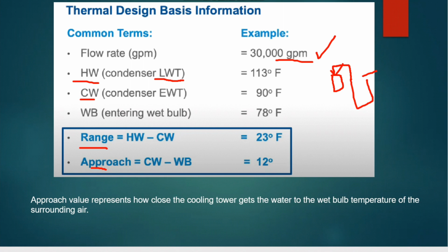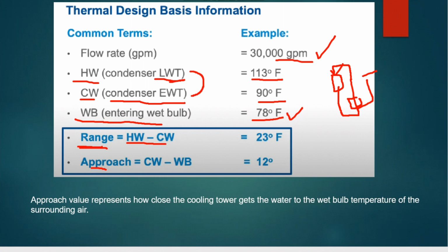This leaving water temperature from the condenser is 113 degrees Fahrenheit. The condenser entering water temperature means, after the cooling tower process, the water which is entering the chiller condenser. This temperature is 90 degrees Fahrenheit. For the wet bulb temperature of that particular region, I assume 78 degrees Fahrenheit for that location. So the range is equal to HW minus CW. HW means the leaving water temperature minus the entering water temperature. This is normally called delta T. This is called the range. Here it is 23 degrees Fahrenheit.